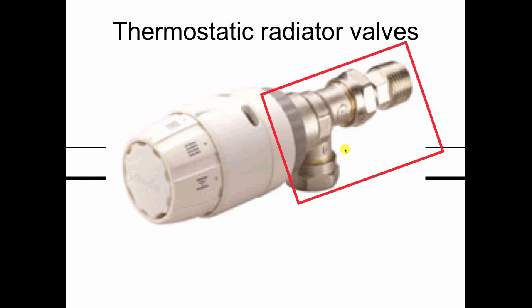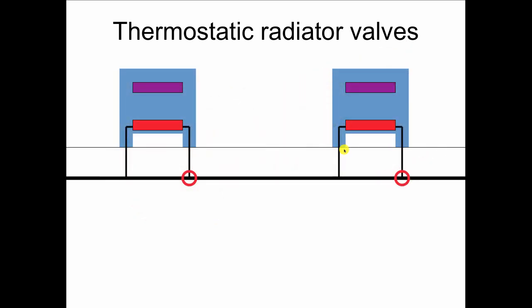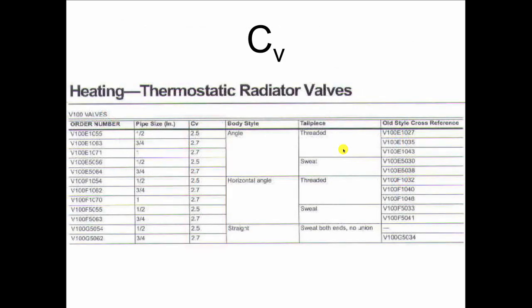But what you have to watch out for when you're buying these for monoflow systems or Diverter-tee systems is what's called the CV because the TRV would go right there. But you've got to look at this thing called CV which is in the catalog as you see here in the Honeywell catalog. It says CV equals 2.5 for the half inch valve and 2.7 for the three quarter inch valve.